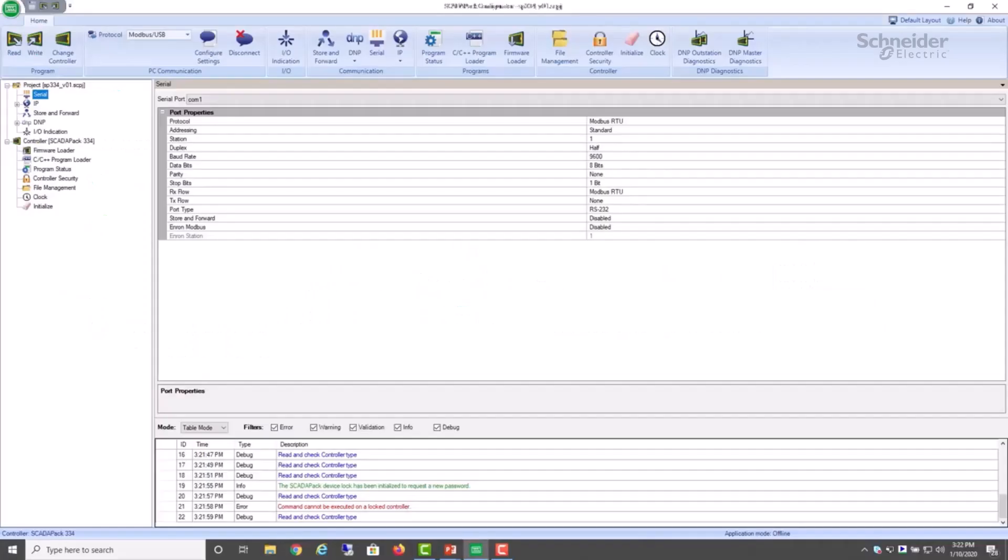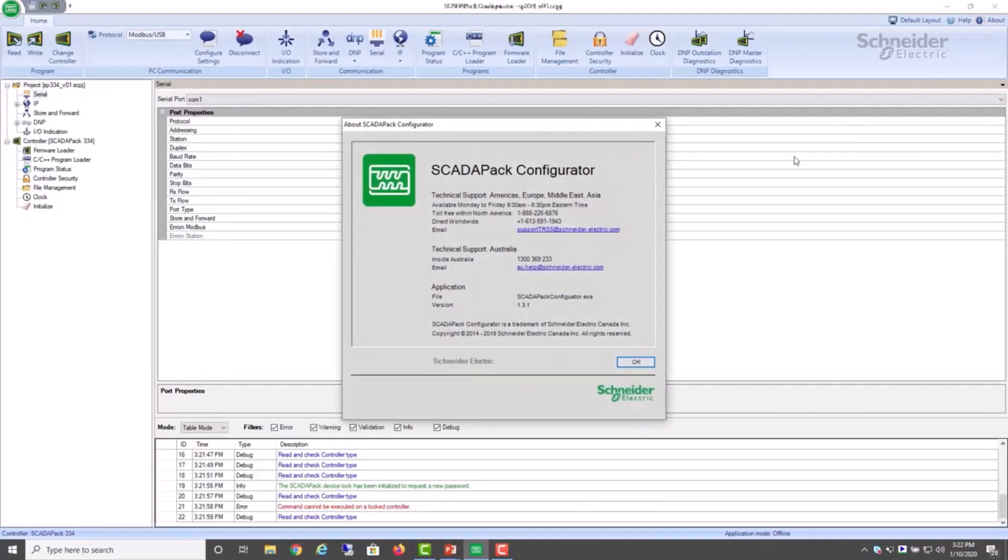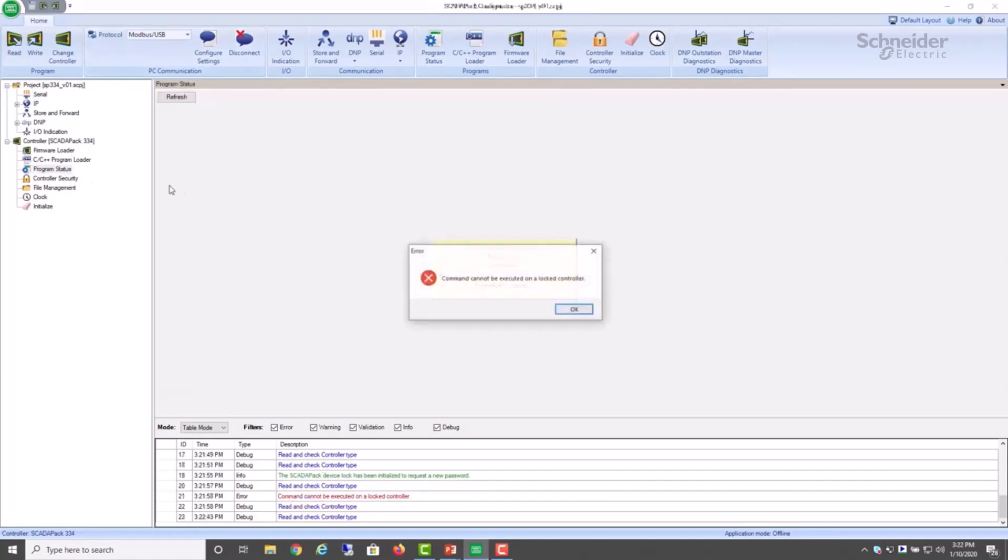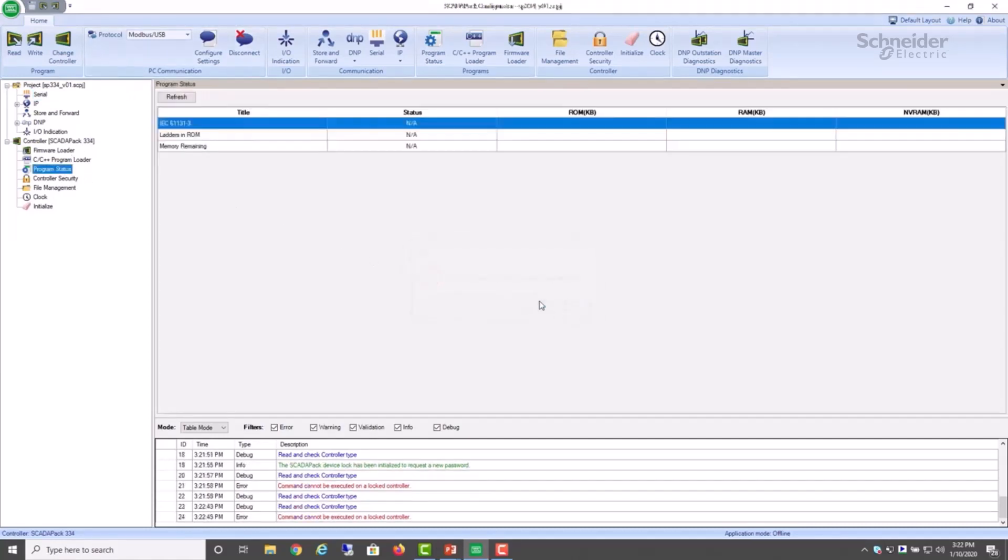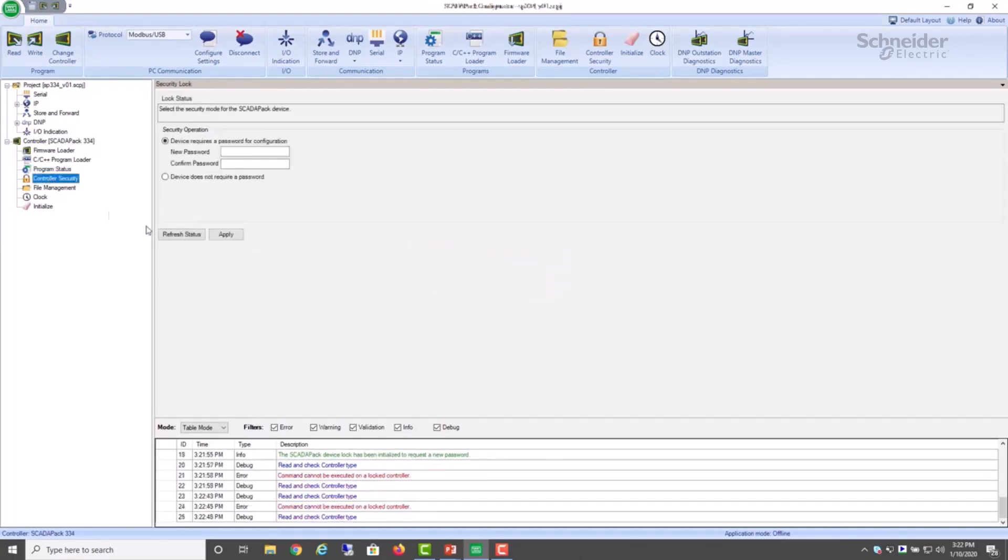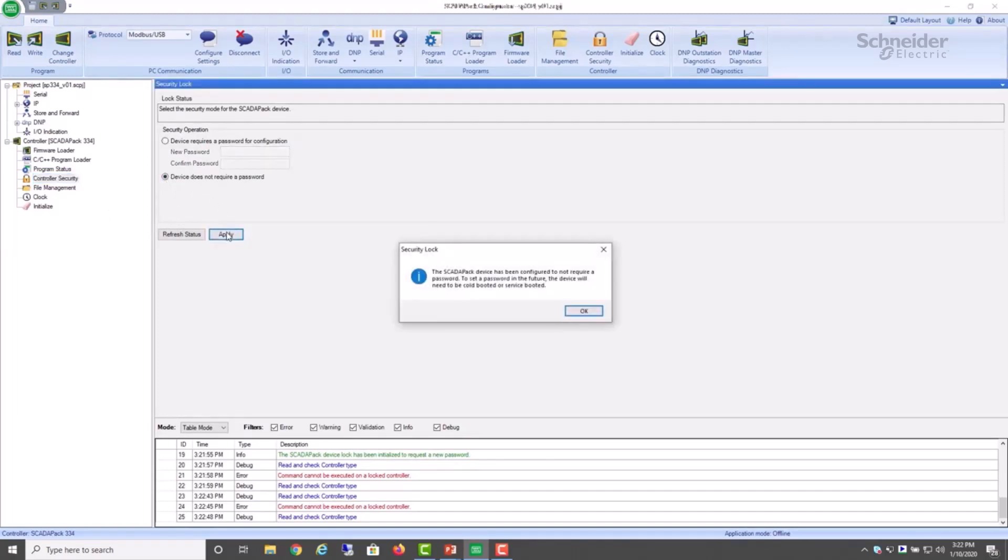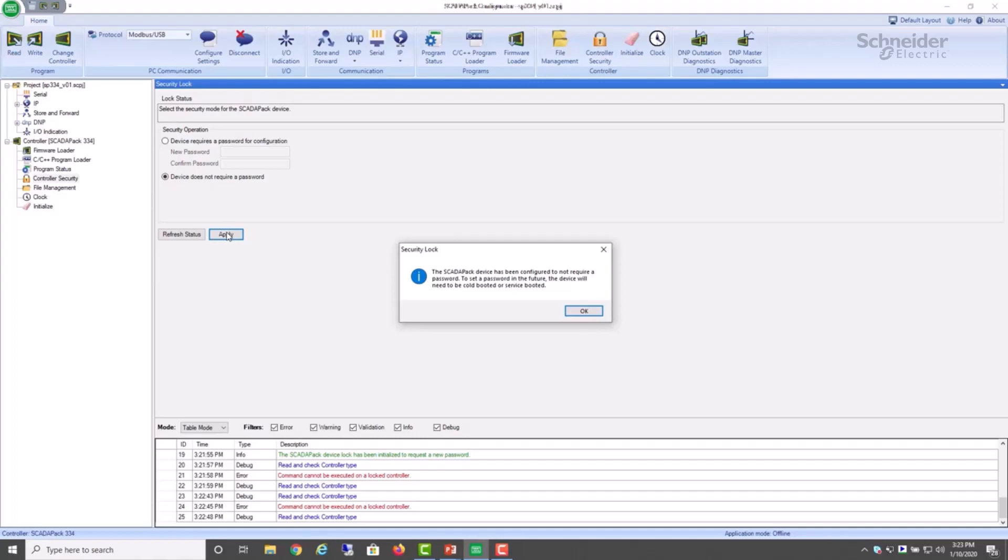This is the updated version, version 1.3.1, and I'm connected over USB to a new SCADAPack 334. If I select a command, I see that it's locked. So we want to go to controller security and to disable the lock, we select device does not require a password and select apply. The information message displayed confirms the desired result. And it also states the requirement for a cold boot or service boot to re-initialize security locking if needed in the future.